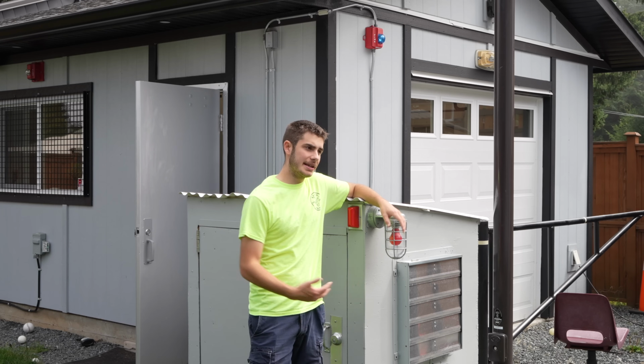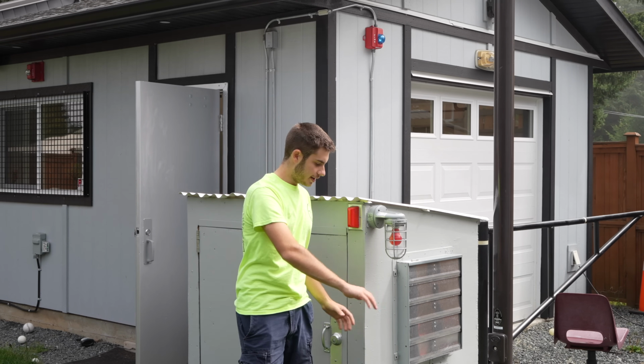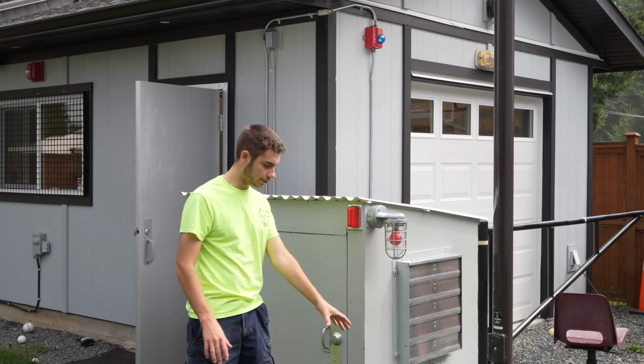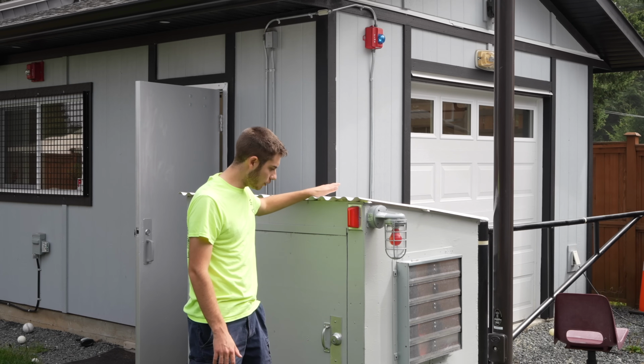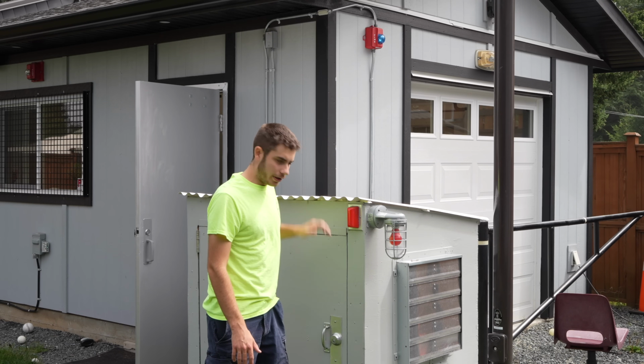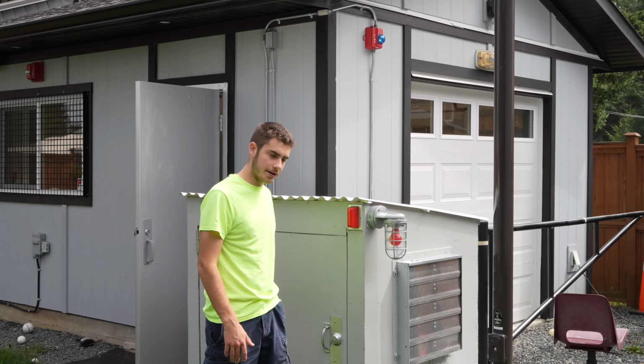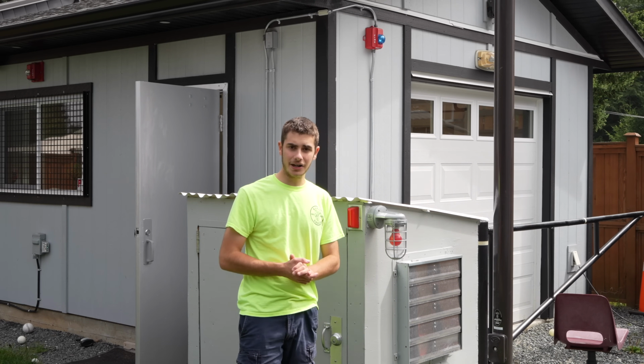But it does seem to make its way to the top, and the air getting pulled over the generator is very centralized in the building. There's kind of, I'm assuming, a column of air right through there. But once something's at the top of the building, like the smoke as it rises, it's really not interfered with by the fan too much as it's lower down, and so is the air intake. So once it's up there, it just collects up there and seems to set that detector off pretty well.